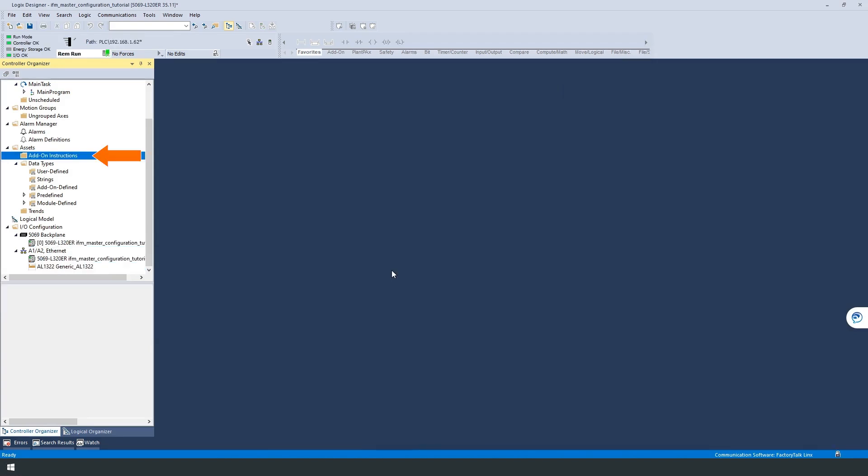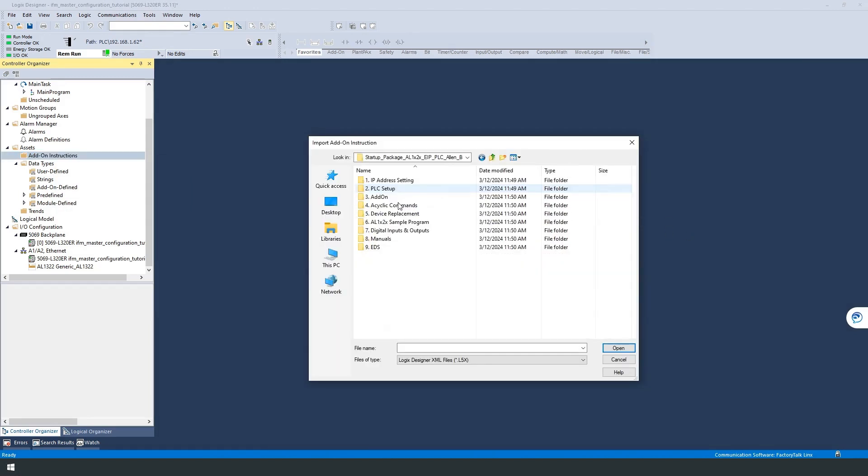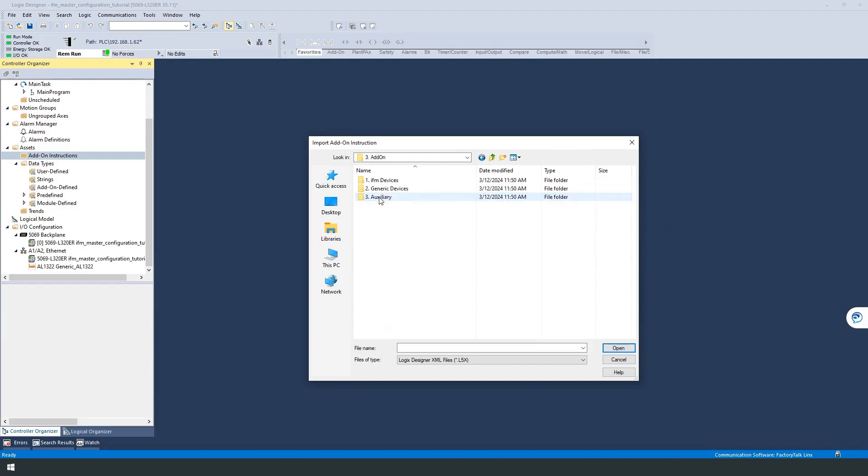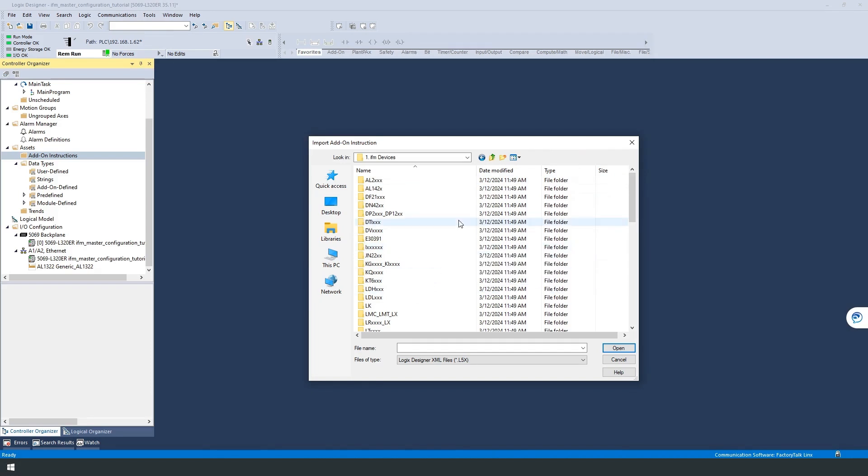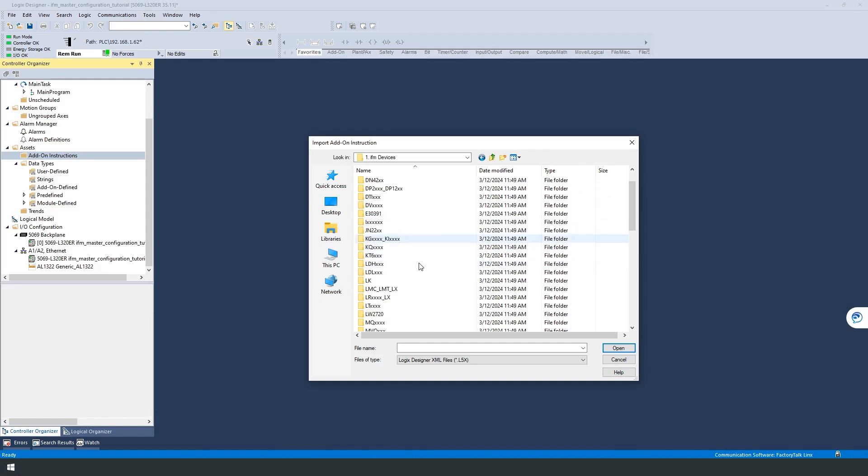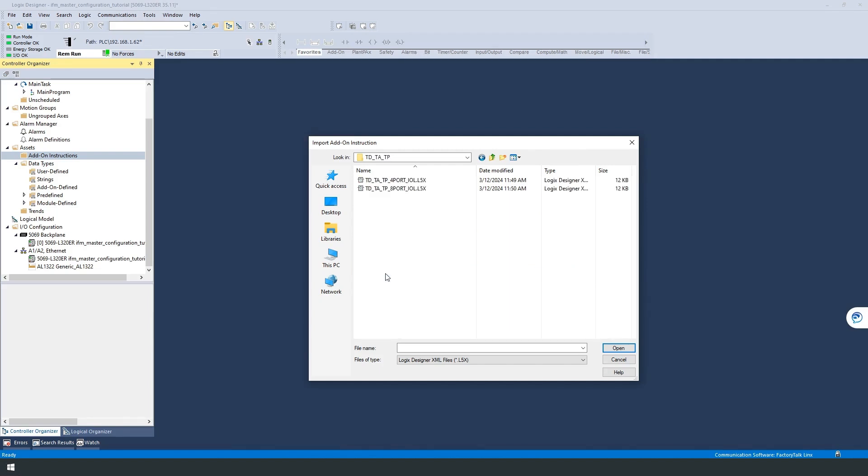The last step is to read out the data from our IO-Link sensor. Navigate to the add-on instruction on the left, right-click, and select Import. An add-on instruction is a predefined function block that is easy to configure and makes the usage of IO-Link data very convenient. They can be used for the input and output of process data, as well as configuration settings. In the already downloaded startup package, we now select the according instruction for our TD28-33 temperature sensor. To do so, select Add-on and IFM devices, pick the device family folder TD-TATP, and select the instruction for our AL1322 8-port IO-Link master.